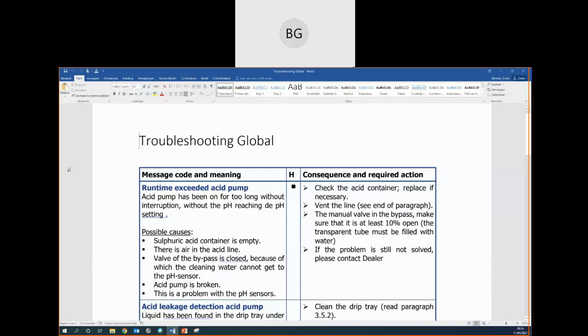For the runtime exceeded pump, the acid pump has been on for too long without interruption, without the pH reaching the pH setting. Possible causes are that the sulfuric acid container or the lye container is empty. There is air in the acid line. The valve of the bypass is closed, because of which the cleaning water cannot get to the pH sensors. This is the tap before the pH sensor block. The acid pump is broken, or there is a problem with the pH sensors. For each of those possible causes, there are consequences and required actions.